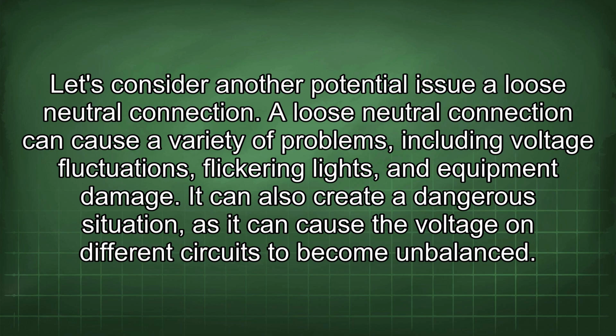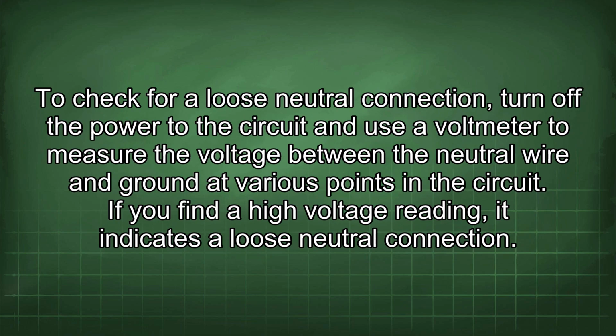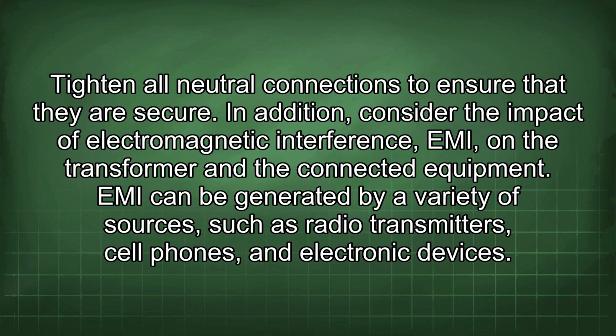A loose neutral connection can cause a variety of problems, including voltage fluctuations, flickering lights, and equipment damage. It can also create a dangerous situation, as it can cause the voltage on different circuits to become unbalanced. To check for a loose neutral connection, turn off the power to the circuit and use a voltmeter to measure the voltage between the neutral wire and ground at various points in the circuit. If you find a high voltage reading, it indicates a loose neutral connection. Tighten all neutral connections to ensure that they are secure.